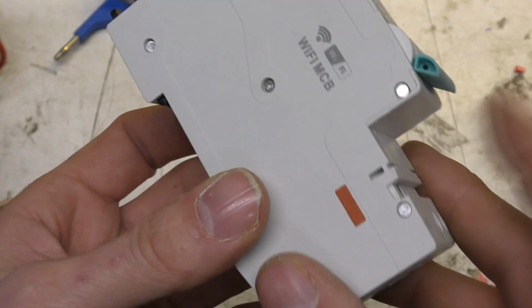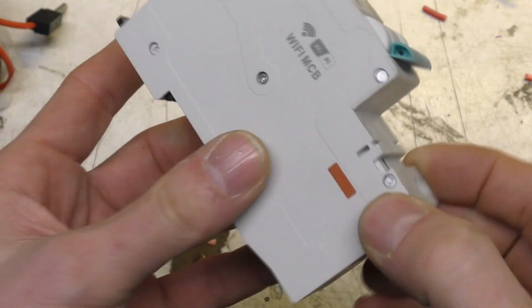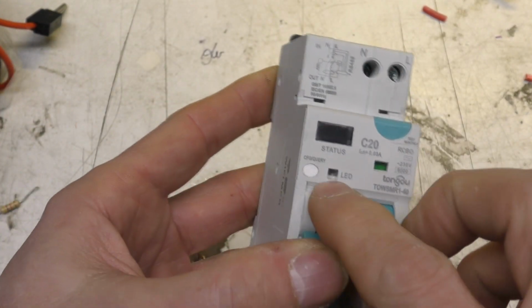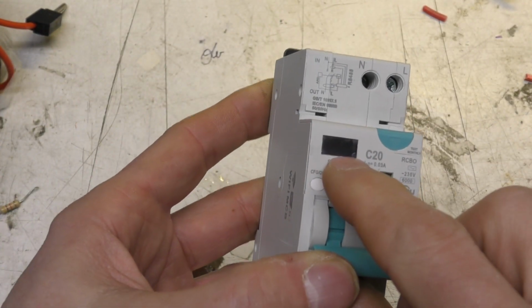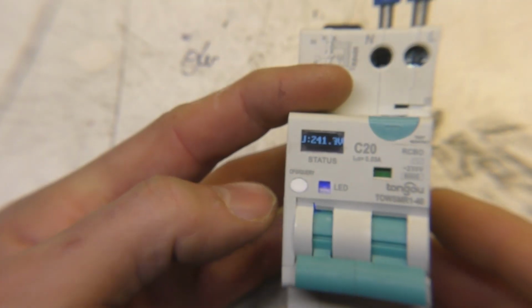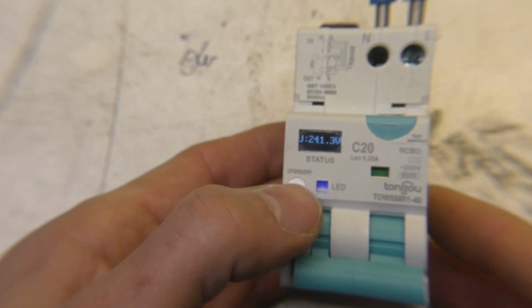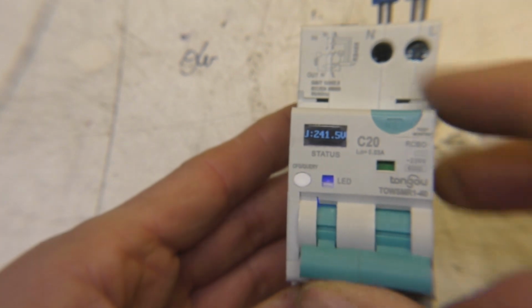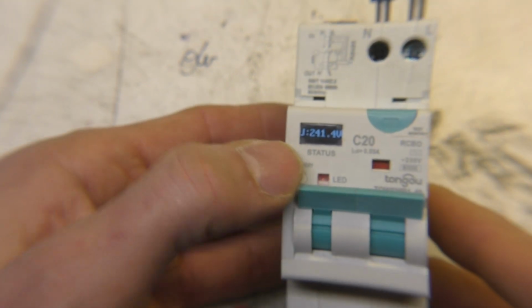There's a section here with a small 4 contacts, which I suspect might be for an RS485 add-on, because there is some mention of RS485. There was a plastic cover strip over this that seems to have fallen off and got lost. It wasn't attached particularly securely. And in addition to the test button, there's also a button here which controls what appears on this little OLED display. So this little OLED display can show various things. This little button here selects what it displays, although when it's switched on it's actually quite annoying to get to it. The actuator blocks it a little bit.